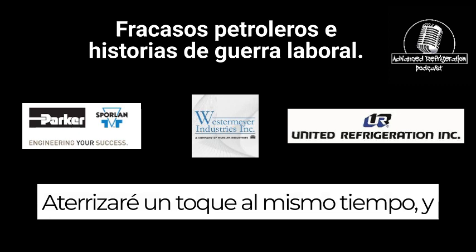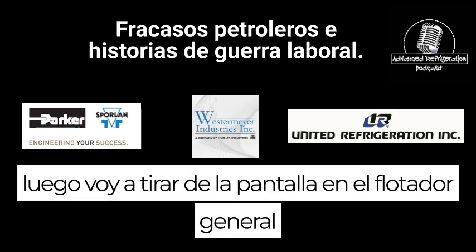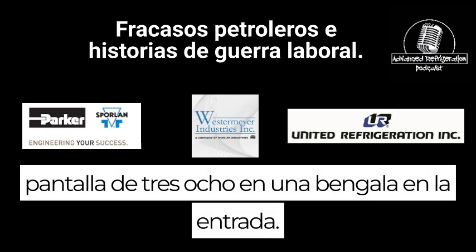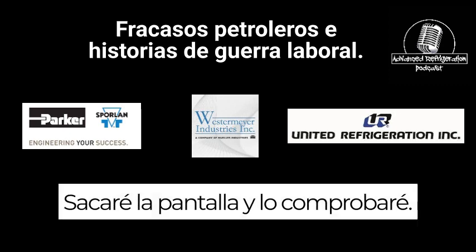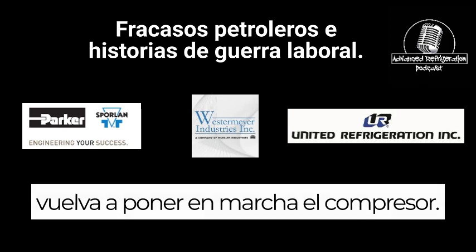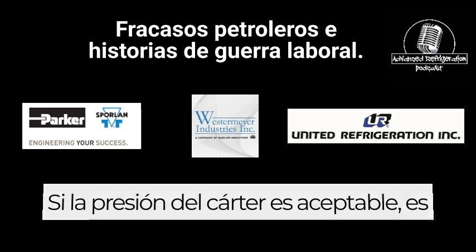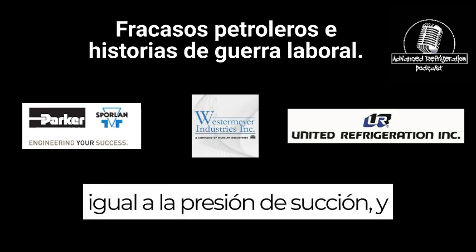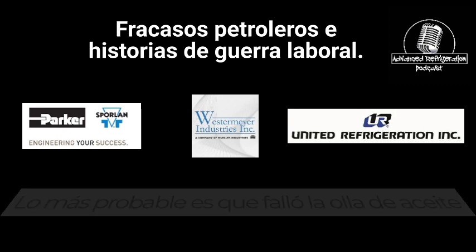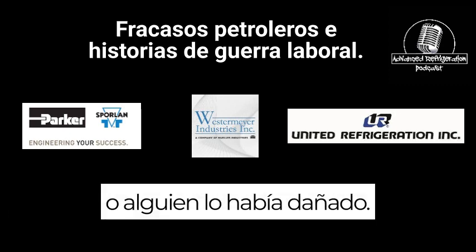I'll add a tap at the same time with the crankcase, and then I will pull the screen on the float. Generally, it's a 3/8 screen on a flare on the inlet. I'll pull the screen and check it. If the screen is clean, I'll start the compressor back up. I will check my crankcase pressure. If the crankcase pressure is acceptable, the same as the suction pressure, and you still won't feed oil into there, more likely the oil pot has failed or somebody had damaged it.